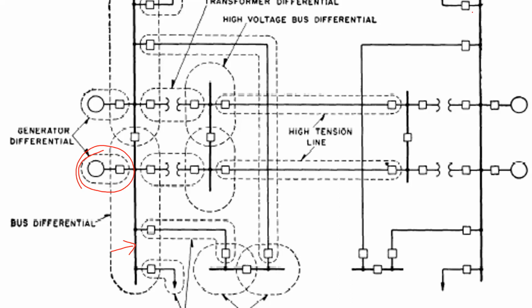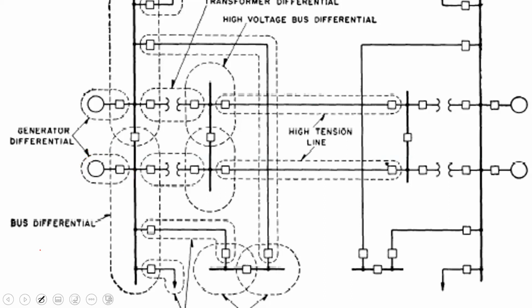So you had the fault on the line, right? So, all right, let me try and use this figure and explain what happened. All right, sir. These are lines. So let us say I had a fault on this line, right? So this is where they had that solid three phase, right? Now that fault, let us say it's closest to this generator. And remember now, we're operating at peak. So all the generators are operating and pumping into the system.